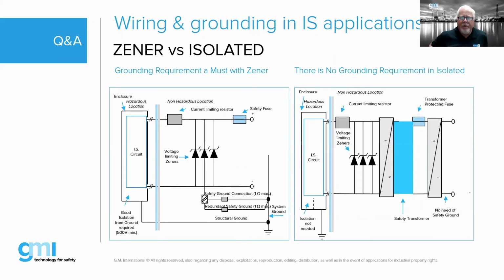So I think we've covered this to an extent, but basically just on the right-hand side, that's a picture of our isolated barrier or an isolator, if you will, galvanically isolated type product. Again, no need for a safety ground. The picture on your left-hand side is the Zener type, typically doing 2 grounds or 2 conductors to our safety ground.